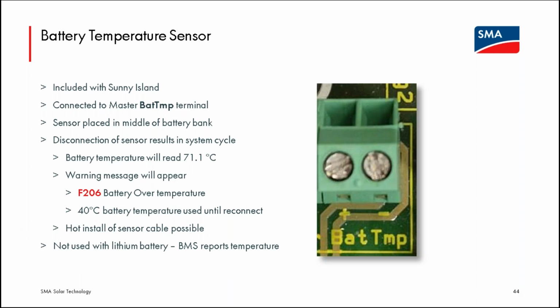For lead acid batteries, the battery temperature sensor is included with the Sunny Island. It only needs to be wired from the master to the battery bank and placed at a place in the battery bank that will give it a good temperature reading. If it is disconnected or becomes cut, the Sunny Island will flag a warning. It will shut the microgrid down briefly and restart it, and then it will run the battery as if it was at a much higher temperature at 40 C, because it wants to be very conservative. It doesn't really know the temperature.